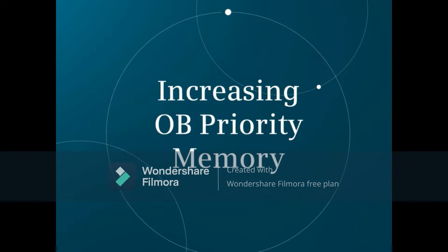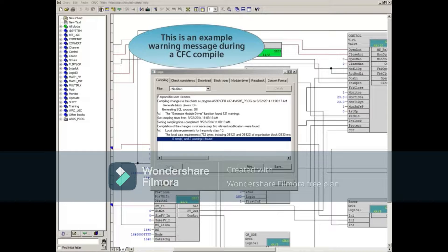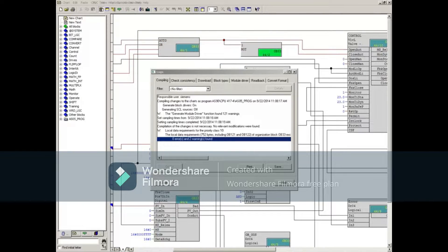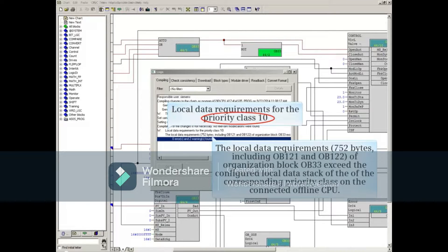This video shows you how to increase the amount of memory available to an OB. Shown is an example warning message during a CFC compile. Note that the initial warning identifies priority 10. The detailed information following points out that there is a local data requirement of 752 bytes of OB33.